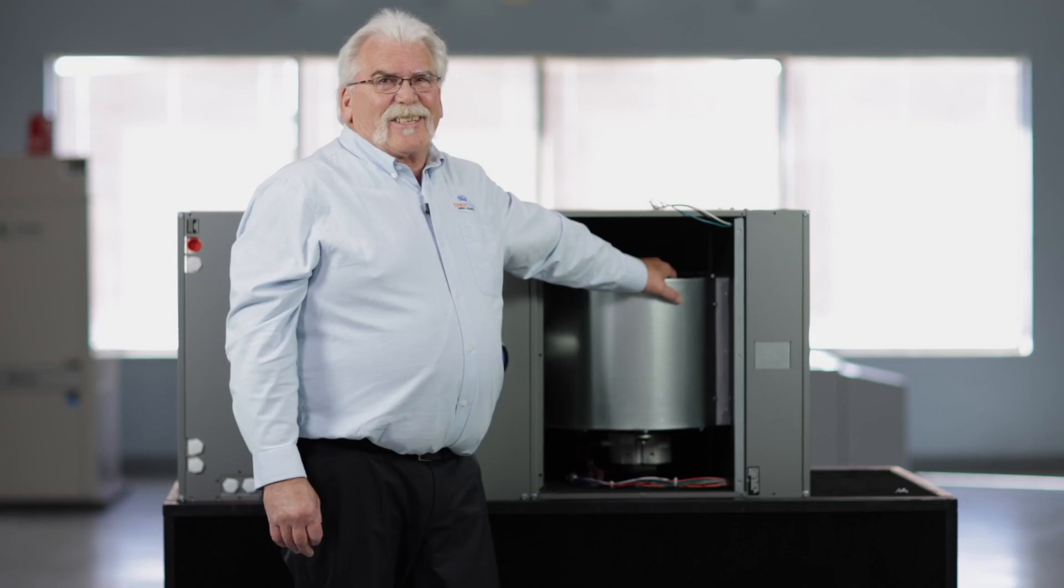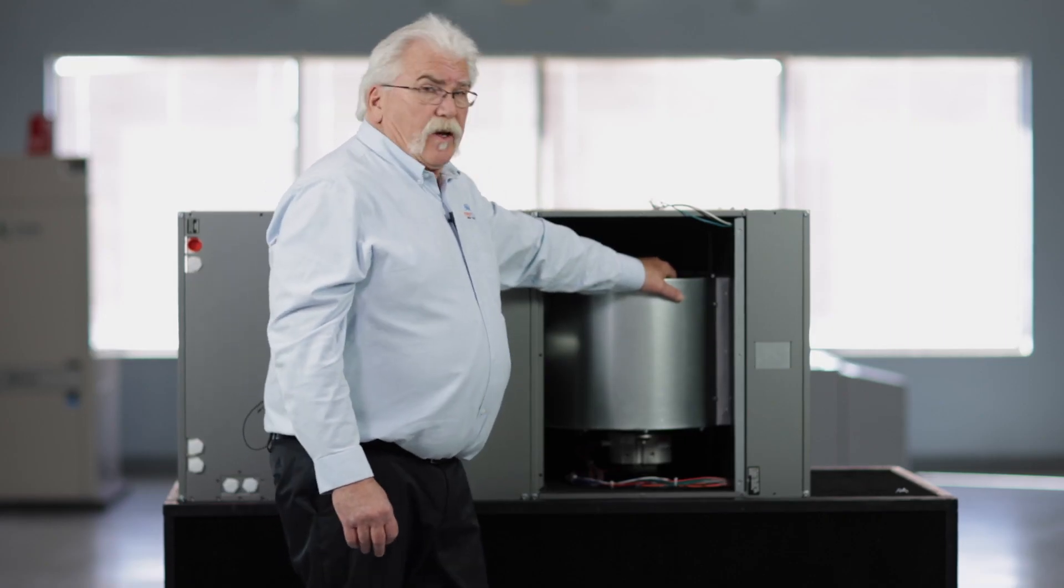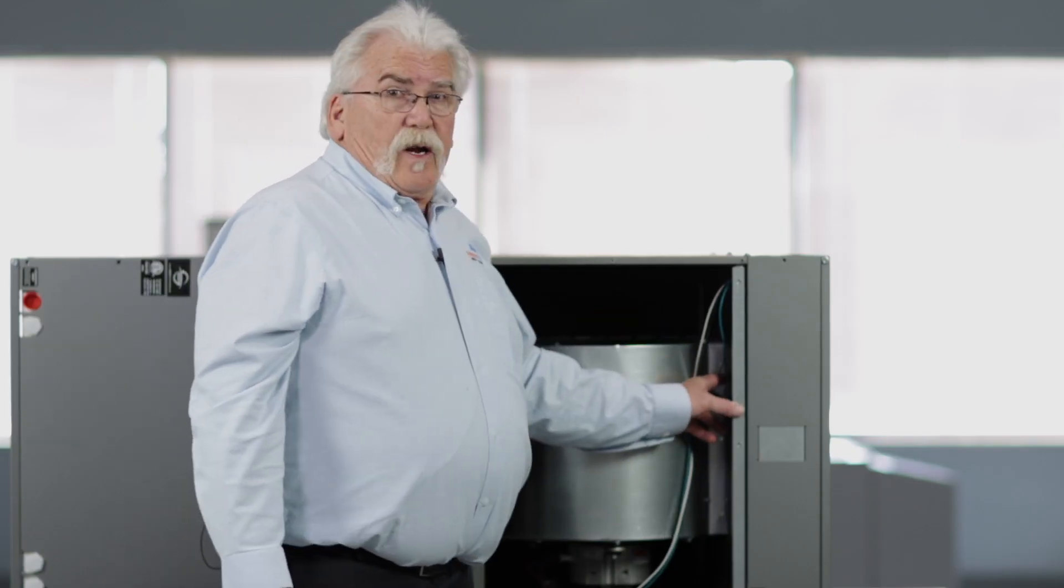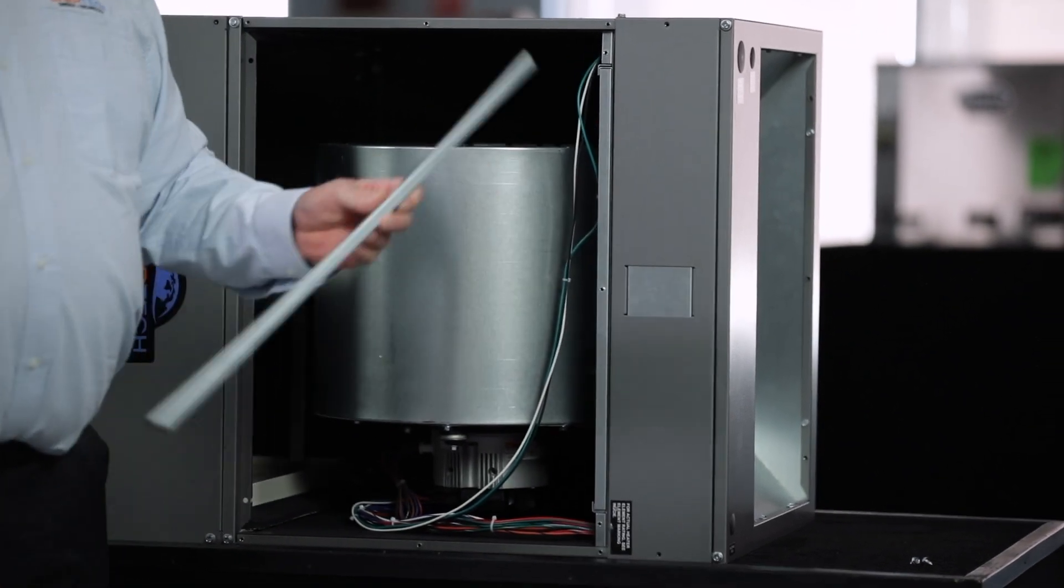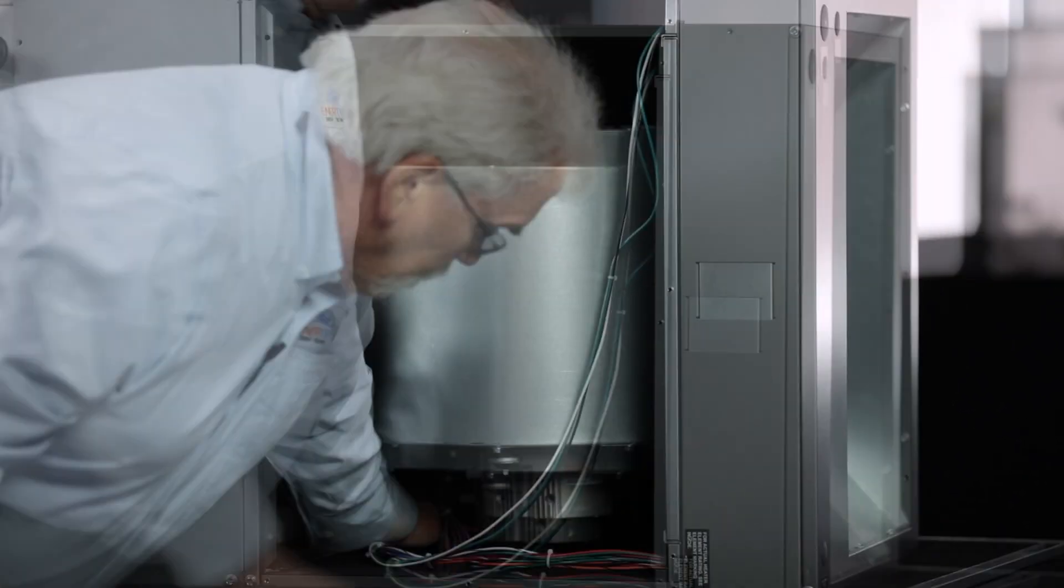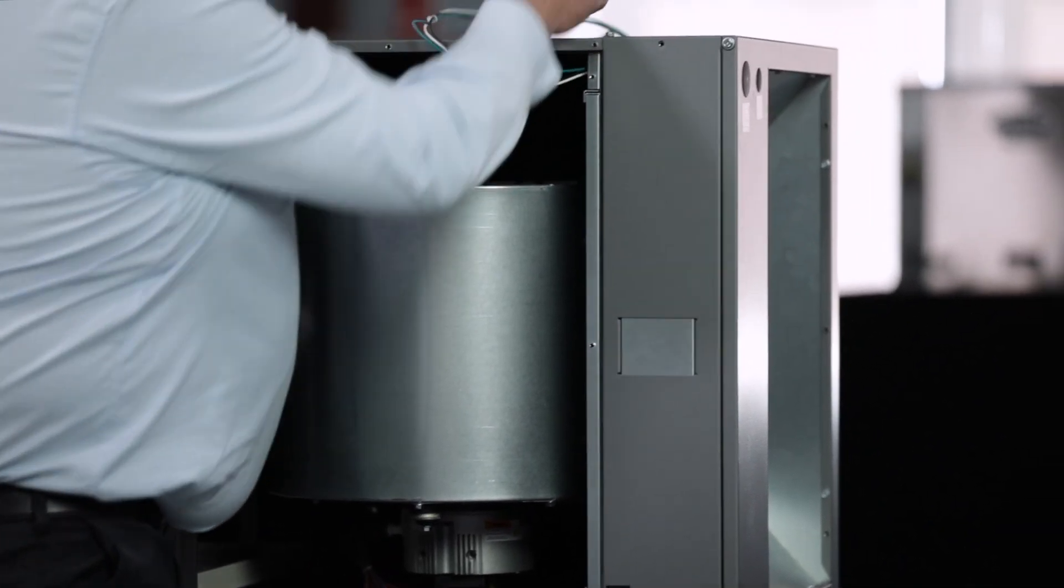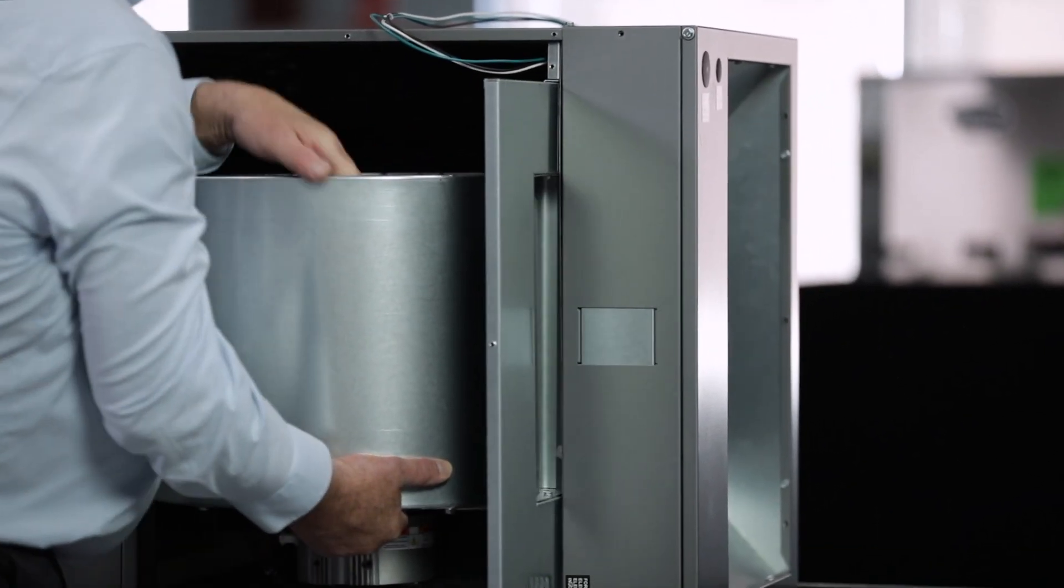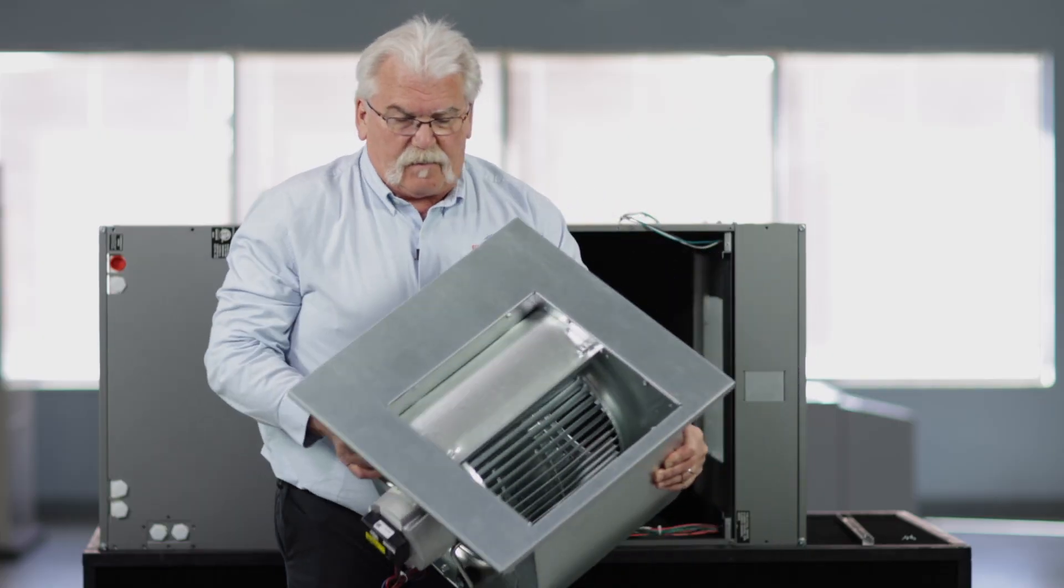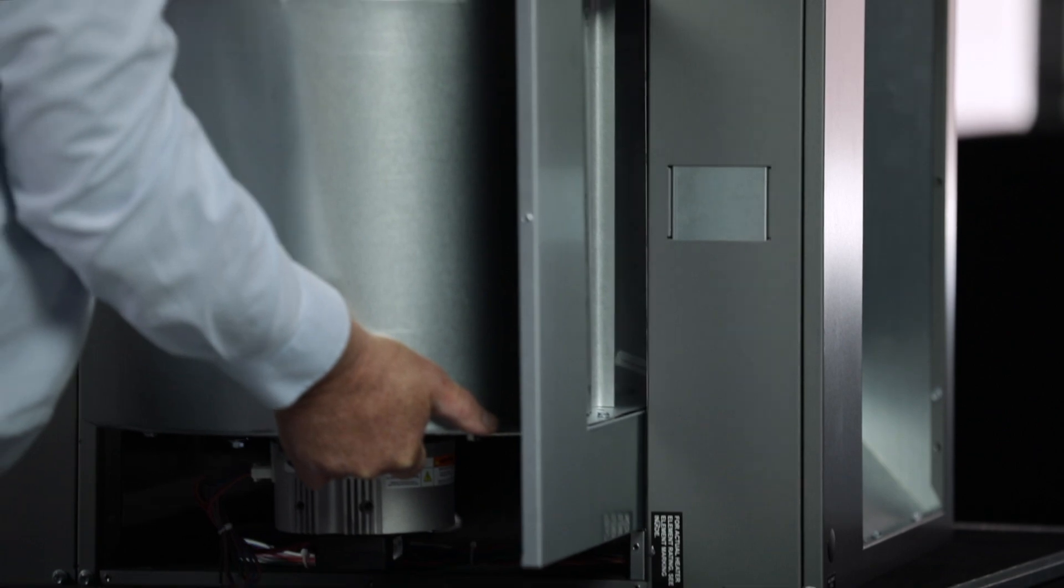It's the same ECM fan motor that's in other Intertech package products. The unit is mounted on a rail. It simply has three screws that you pull out to pull off this retainer. You unclip the wiring connections and can slide the whole blower assembly out of the system for easy maintenance and repair.